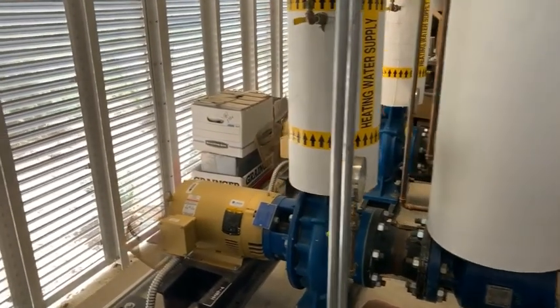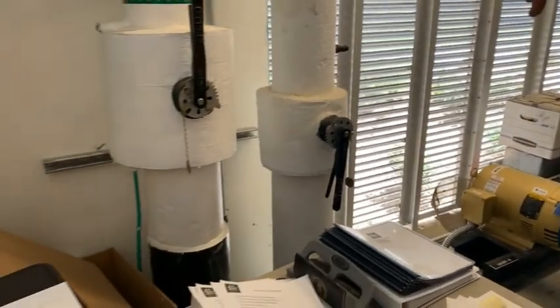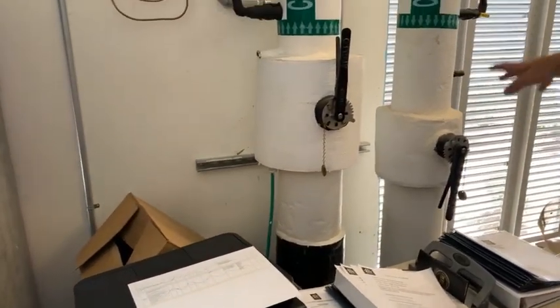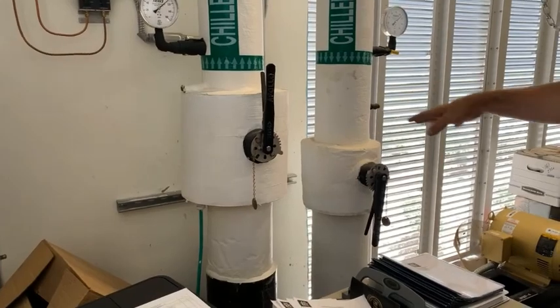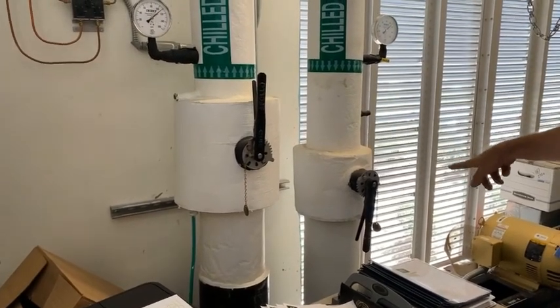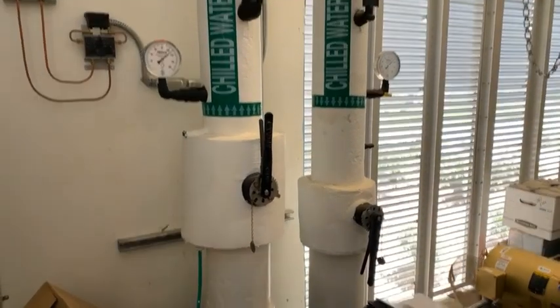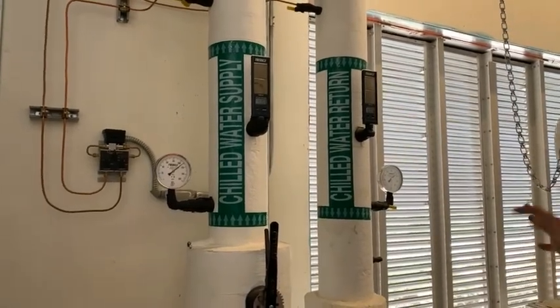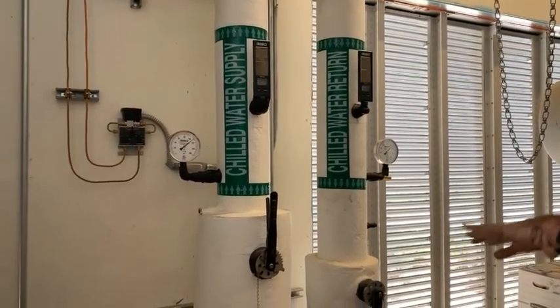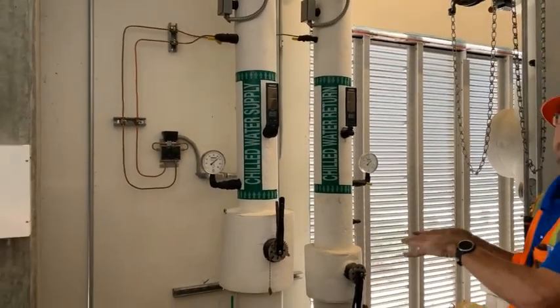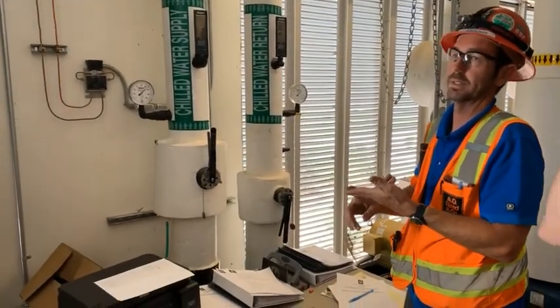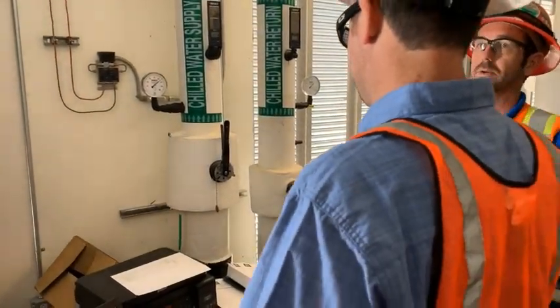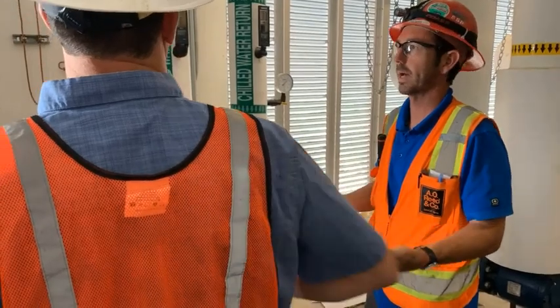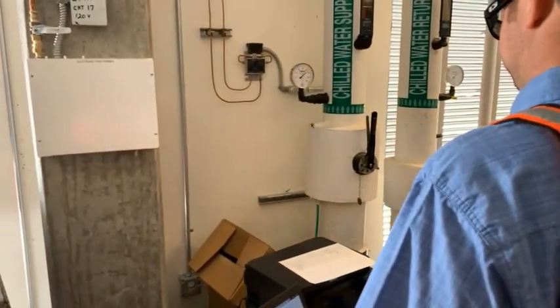I don't believe we talked about this building. We're in building B still, mechanical room. We have the main chilled water shutoff valves over here, okay? Supply on this side, return on the right. So if you had a main chilled water problem, these would be your main shutoff valves. Remember, if you shut these valves off, you lose cooling to the telecoms and electric rooms. You'd have to provide temporary cooling with like a MovinCool or some type of device like that. Because you'll lose it in the corridors too.